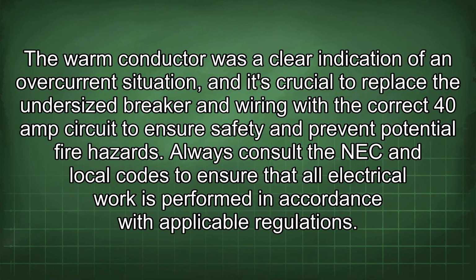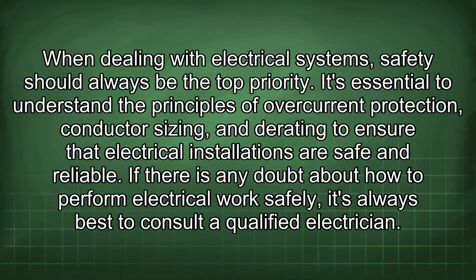The warm conductor was a clear indication of an overcurrent situation, and it's crucial to replace the undersized breaker and wiring with the correct 40 amp circuit to ensure safety and prevent potential fire hazards. Always consult the NEC and local codes to ensure that all electrical work is performed in accordance with applicable regulations. When dealing with electrical systems, safety should always be the top priority.